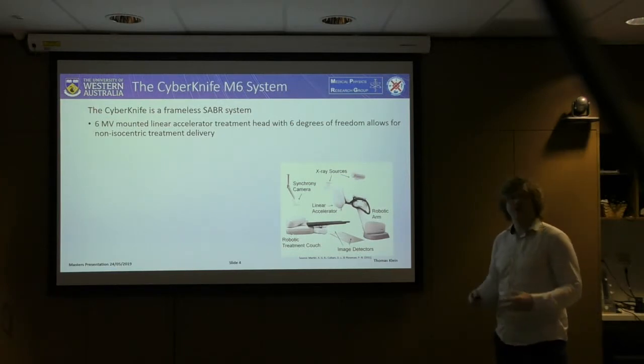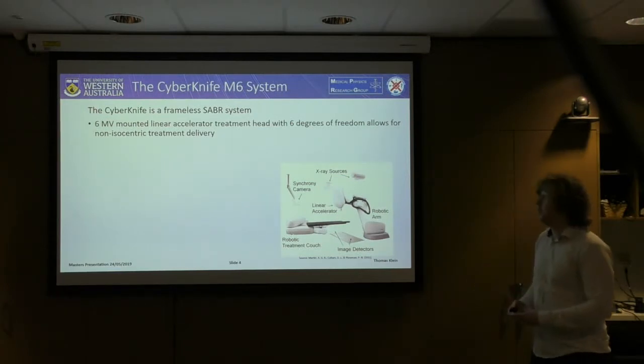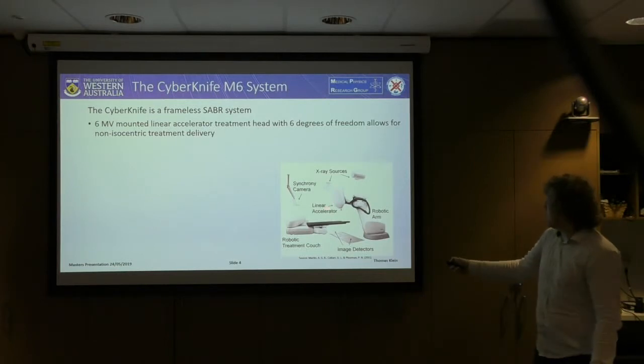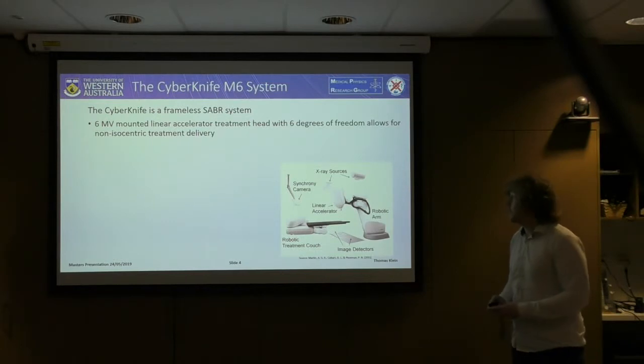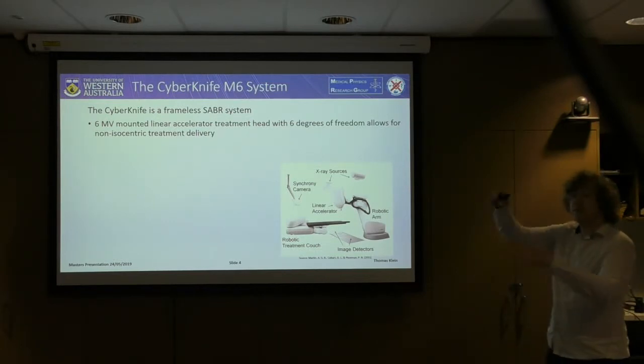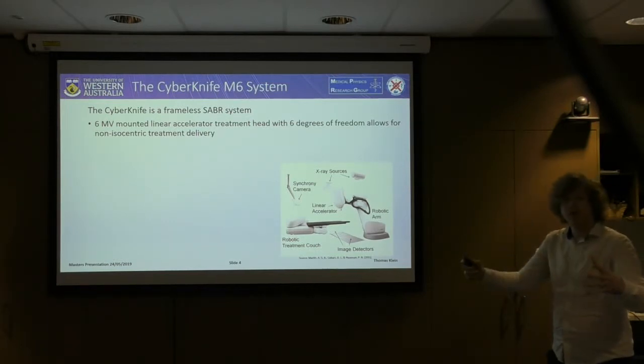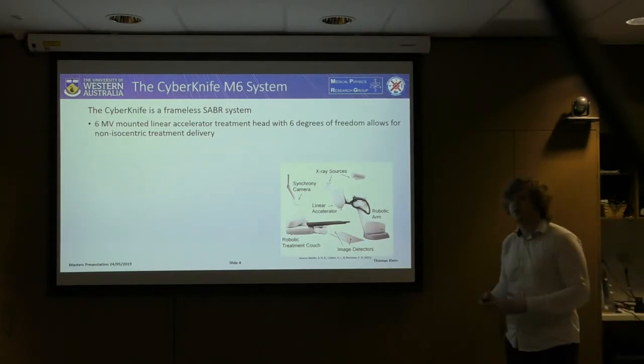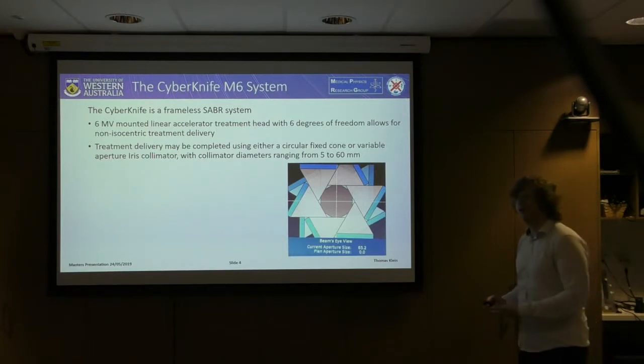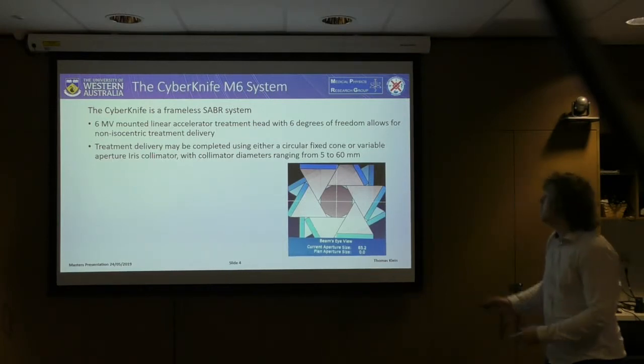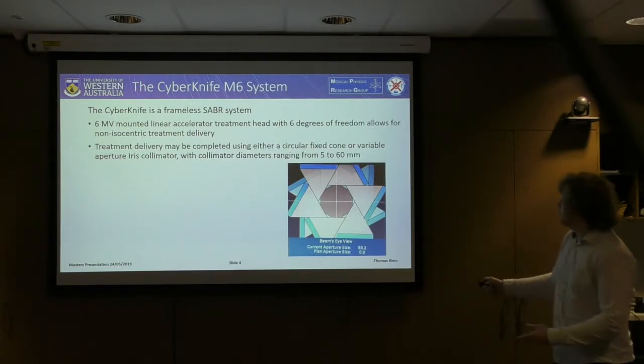The CyberKnife system is a frameless stereotactic ablative radiation therapy system with a 6MV mounted linear accelerator placed on the end of a robot with 6 degrees of freedom. This linear accelerator can be moved to a discrete number of nodes and facilitates non-isocentric treatment delivery from any desired angle. For this project we had circular fixed cone collimators as well as the variable aperture iris collimator, and we used the variable iris collimator for all treatment deliveries with collimator diameters ranging from 5 to 60 millimetres.